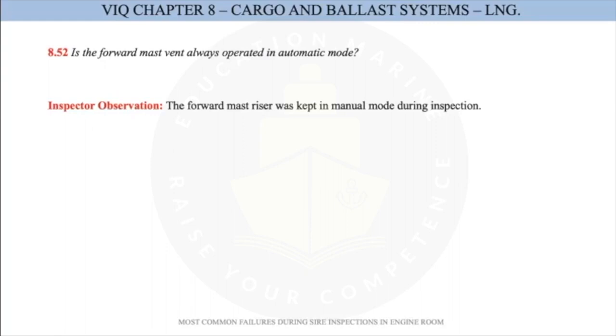Sometimes some people put this on manual mode, maybe to avoid opening when they have high pressure in the tanks and this pressure is under control. Let's say it's higher, 225 to 230, but they can see that the curve is going down, they are consuming, and to avoid opening, they just put it on manual. Maybe they forget to put it back, but it should be on auto mode.